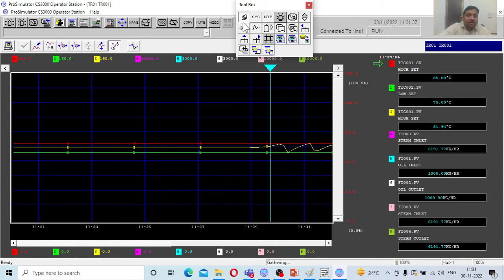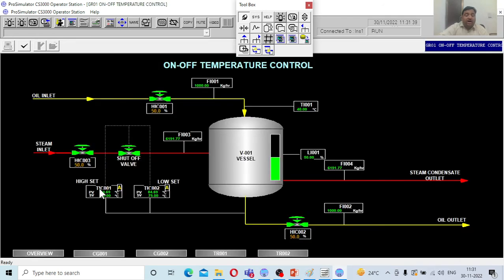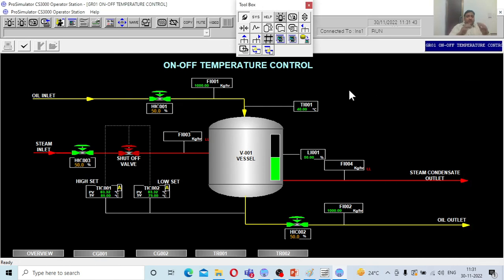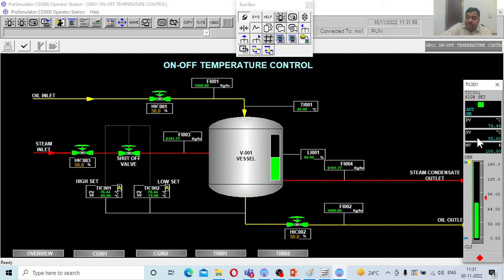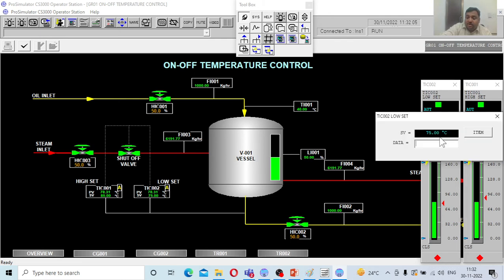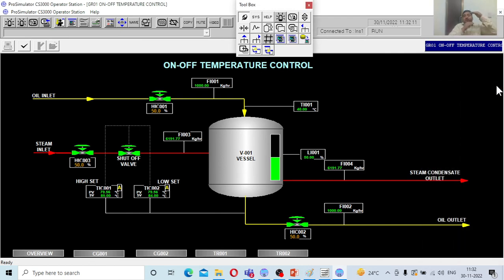Let me show one more thing — I am going to change the set points. Currently, the low set is 75 and the high set is 85. The moment I reduce the boundaries between them, it will cause problems for the controller. I will change the low set point to 84, so now the high set is 85 and the low set is 84. With such narrow boundaries, you will see very frequent on and off switching of the control valve.